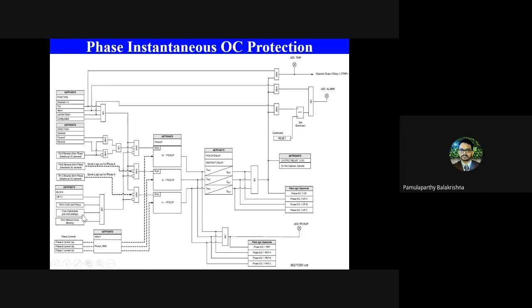Until the auto reclosure executes those 3 to 4 cycles of operation, this function cannot take any action. Another option is that the user has manually blocked this function from operating, and then also it cannot take action. So in a practical condition, the protection logic not only has to look at what it has to execute or on what signal it is operating, but it also has to consider various other practical conditions before executing any action like tripping the breaker or giving an alarm to the user. Actually, I have some more content, but considering the time, I would like to stop here.